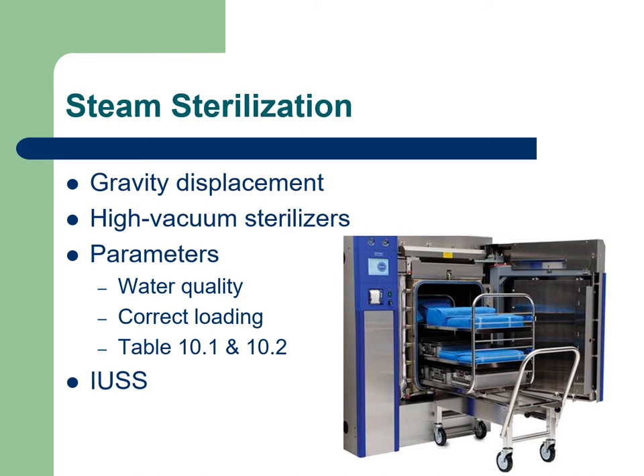With gravity displacement, air gets pushed out by gravity, just like it implies, gravity displacement. The gravity displacement system injects steam into the chamber and displaces the air. It pushes it down. Gravity is causing it to move downward towards the drain. This takes longer to do it this way. The high vacuum sterilizer, as it implies, has a vacuum that removes the air.